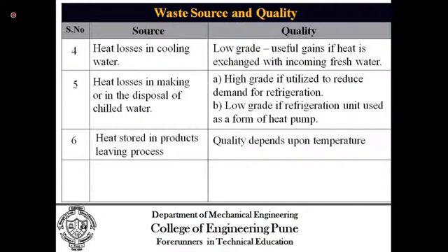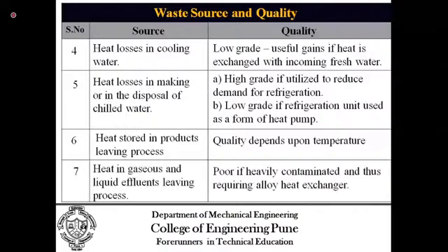Heat in gaseous and liquid effluents leaving the processes. Hot gases and hot effluents are released to the atmosphere or to the water bodies. But before that, you must be knowing that in our India, there is a restriction on the temperature at which these effluents can be released to the water bodies, and if I'm not wrong, it is something like 40 degrees Celsius. So if the effluent is at a higher temperature, then it is required to cool it down. While cooling it down, the heat content of the effluent can be utilized for getting some positive work.